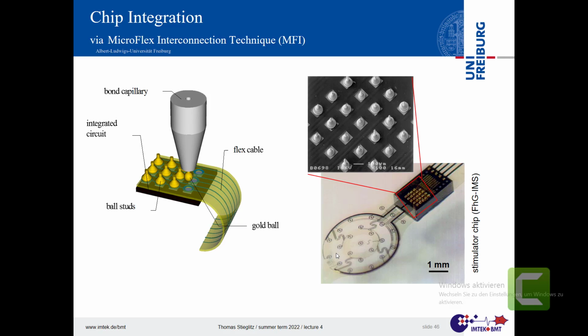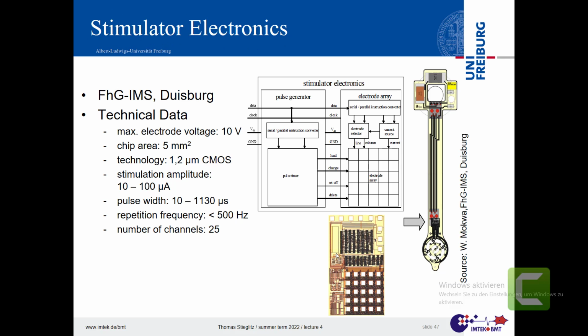I love that picture for the sake of showing you that dimension here. That was one of the old chips, a standard one, not thinned down. I mean, that's a nightmare, having a 500 micron thick electronic circuitry on a 10 micron thick foil. That's completely stupid. Nowadays you can thin those chips down to 30 microns, and then you have a really nice and shallow transition between electronics and supporting substrate. The stimulator could do up to 100 microamps and variable pulse width and a high repetition frequency to cover high spatio-temporal excitation of nerve cells.